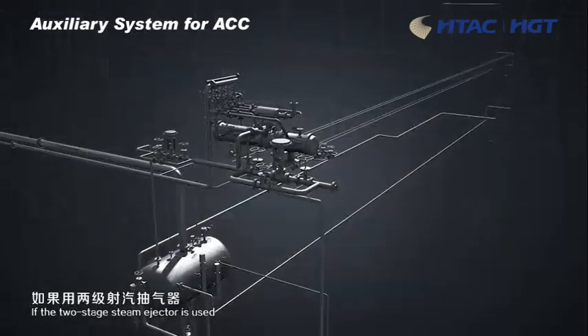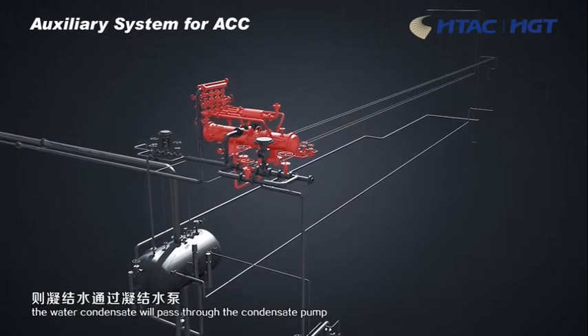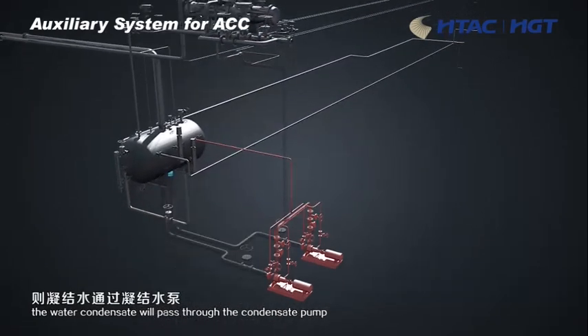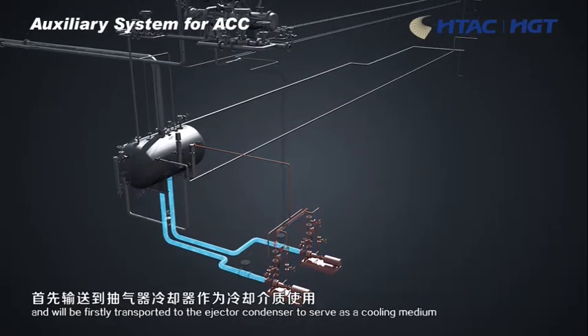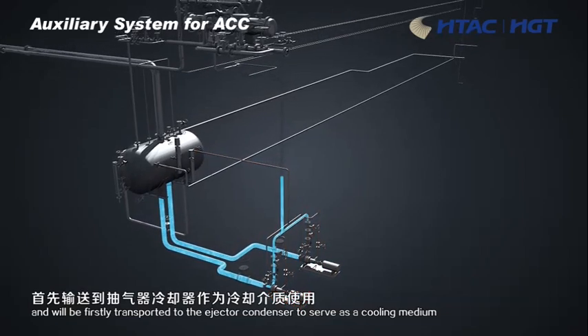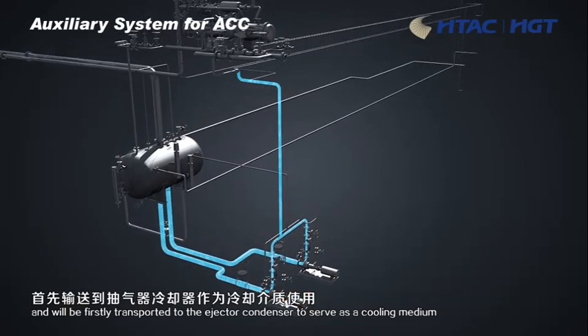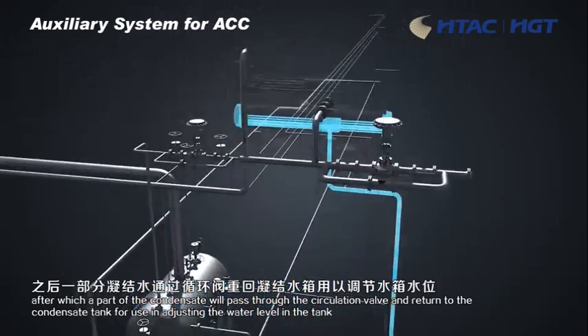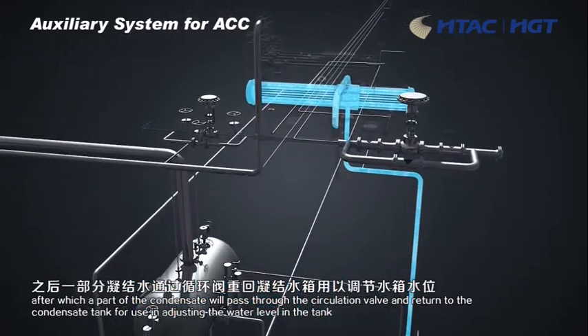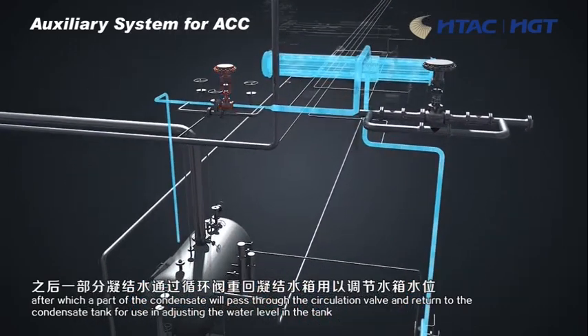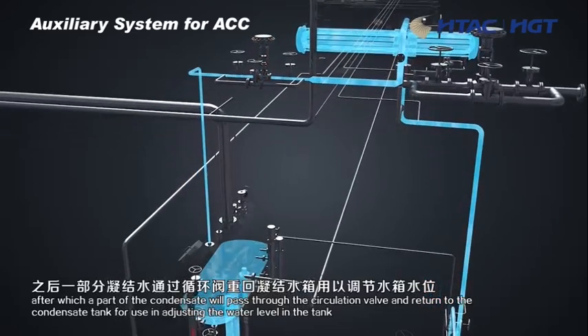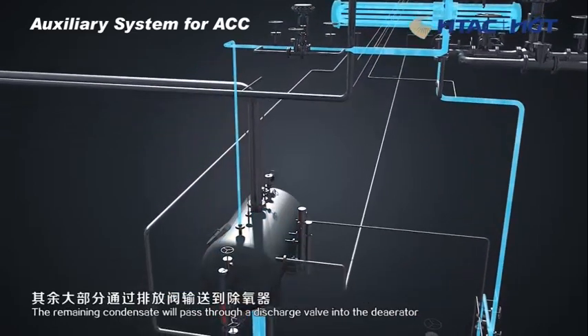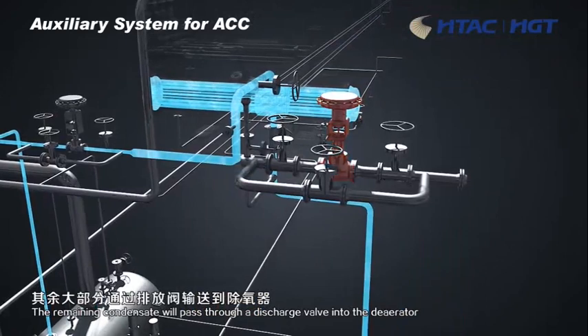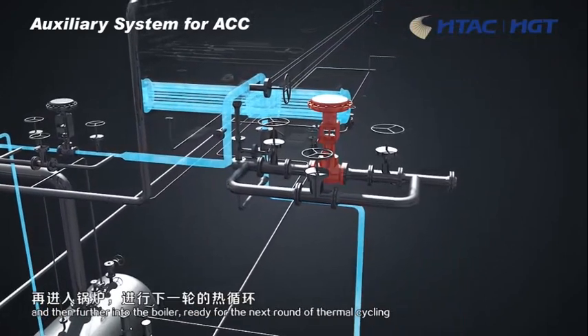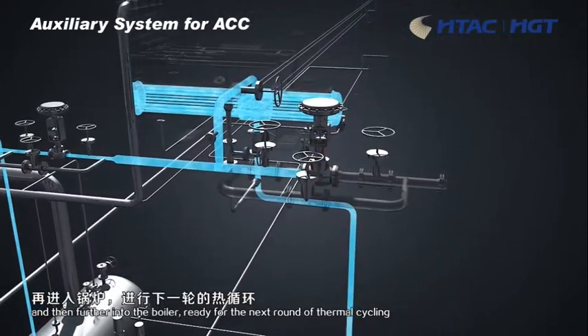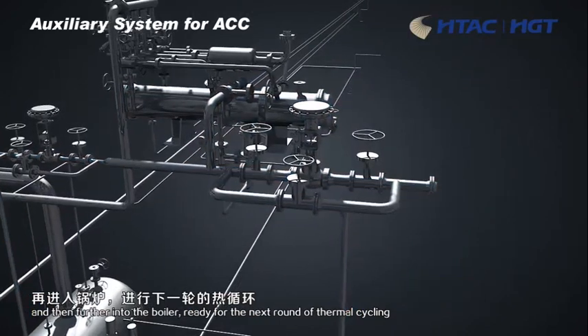If the two-stage steam ejector is used, the water condensate will pass through the condensate pump and will firstly be transported to the ejector condenser to serve as a cooling medium, after which a part of the condensate will pass through the circulation valve and return to the condensate tank for use in adjusting the water level in the tank. The remaining condensate will pass through a discharge valve into the deaerator and then further into the boiler, ready for the next round of thermal cycling.